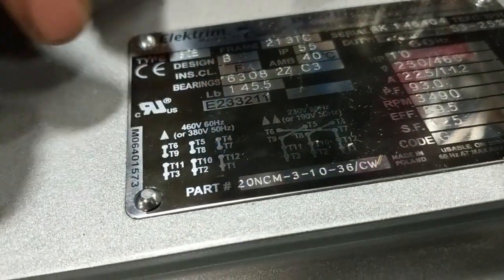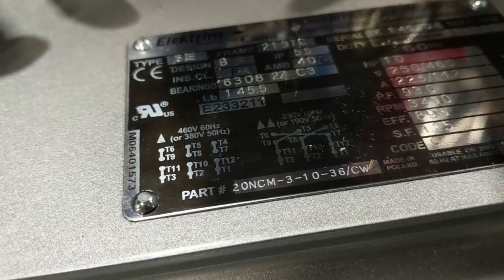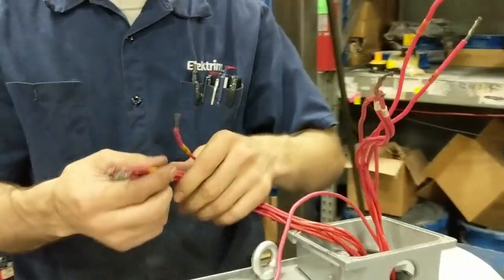We're going to be working with the 20NCM-3-10-36/CW car wash motor and we're going to be wiring it for 460V Delta. We're using Delta because it is a 12-lead motor and must be wired with 12 leads.